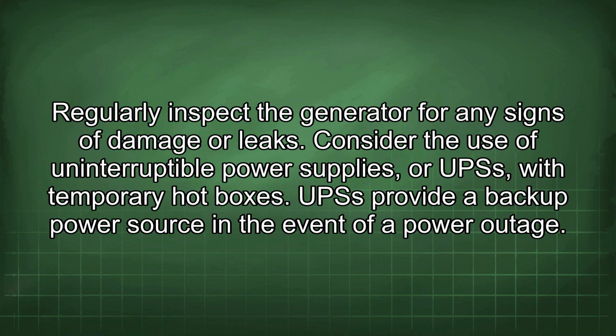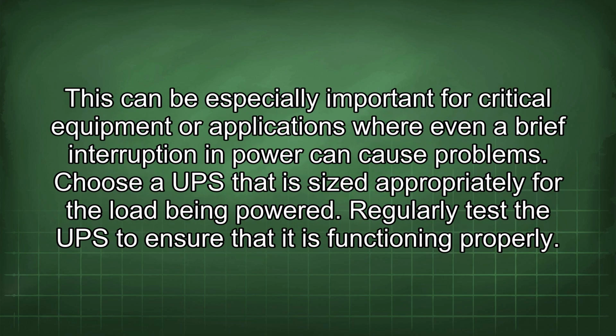Consider the use of uninterruptible power supplies, or UPSs, with temporary hotboxes. UPSs provide a backup power source in the event of a power outage. This can be especially important for critical equipment or applications where even a brief interruption in power can cause problems. Choose a UPS that is sized appropriately for the load being powered. Regularly test the UPS to ensure that it is functioning properly.